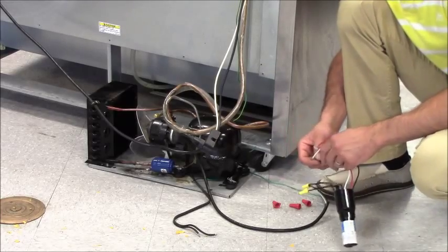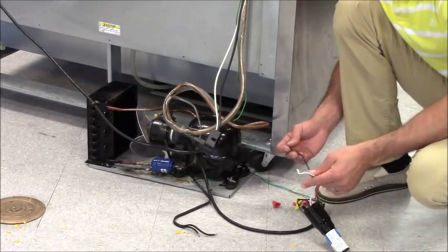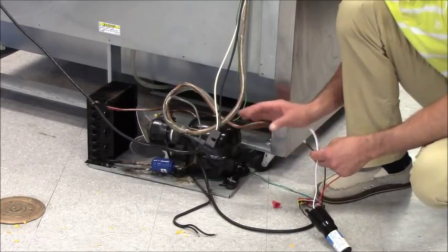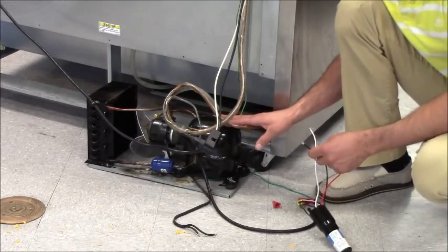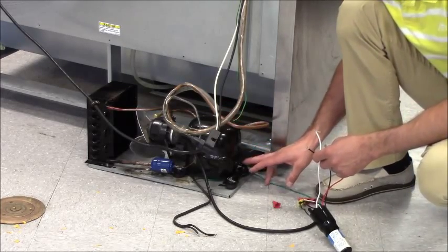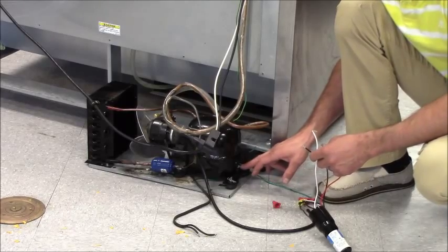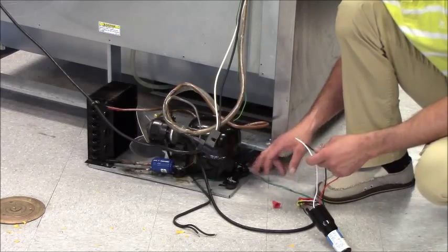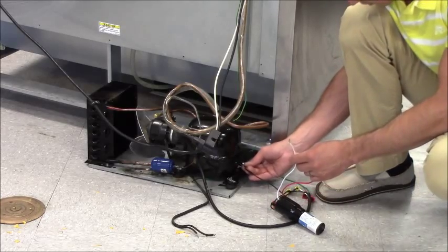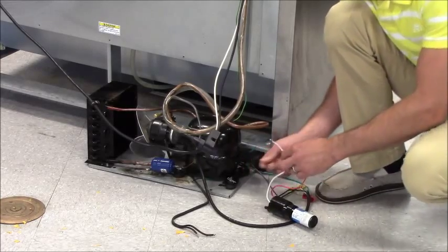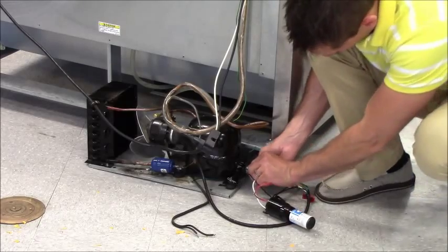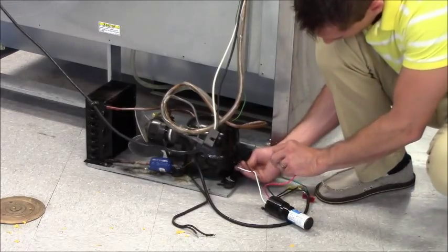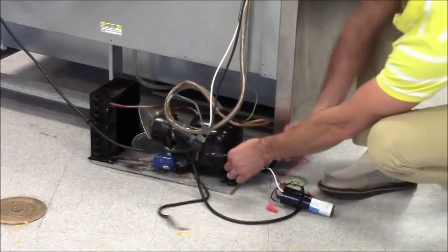So now comes the complicated part. What we're going to do is take these three wires and apply them to the compressor. If you look at the compressor, there's going to be three pins: C, S, R. The C is going to be your black wire. The S is going to be your white wire. The R is going to be your red wire.